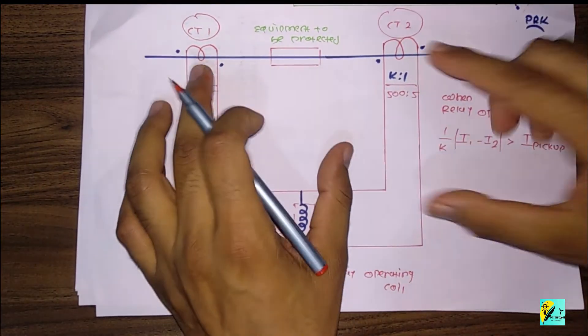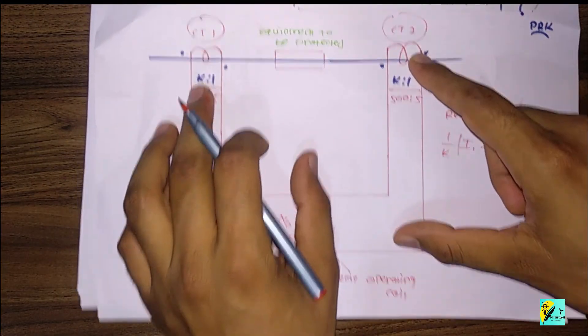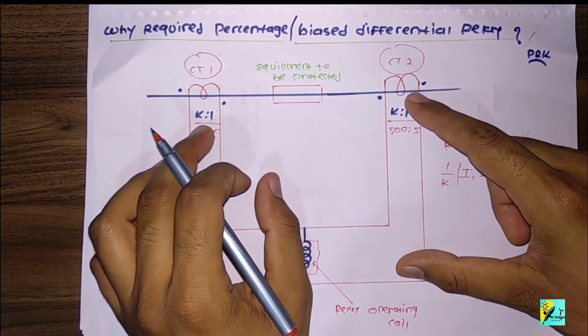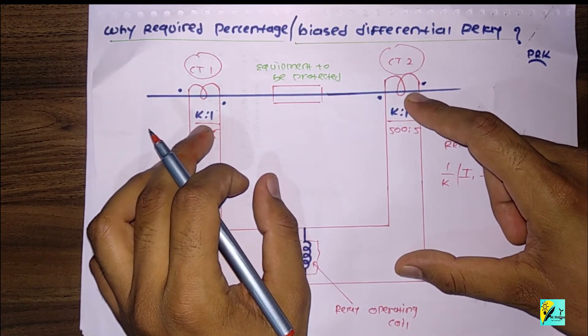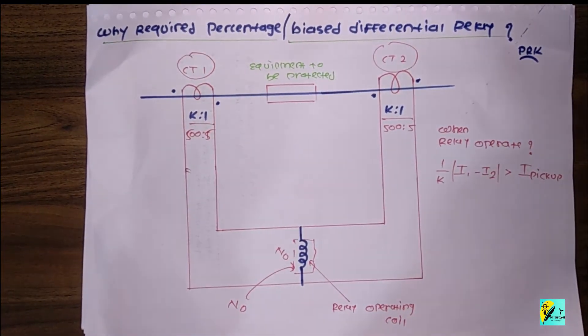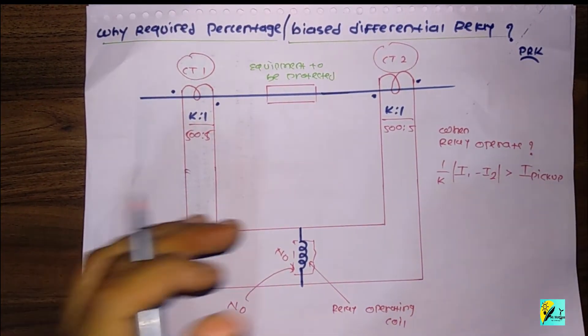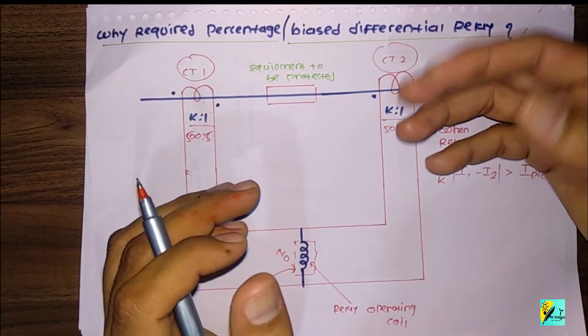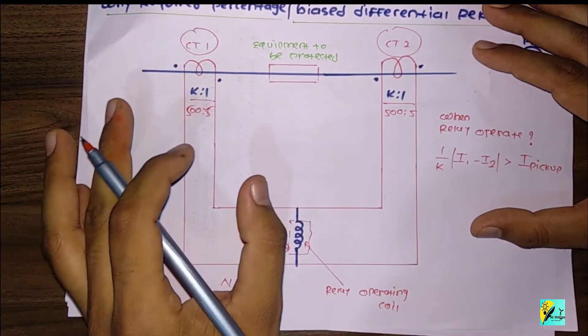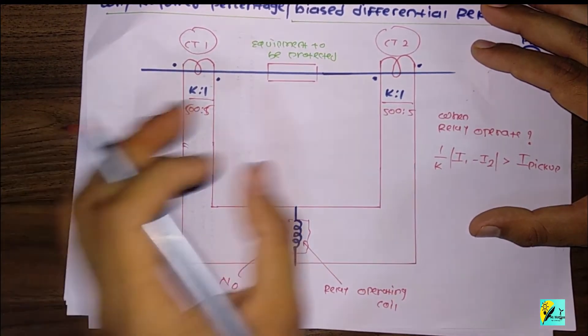If these two transformation ratios of the two CTs are not equal and identical, then the secondary currents will not be equal obviously. So if there is no fault, I1 should equal I2, but their secondary currents will not be equal if the transformation ratios are not equal.